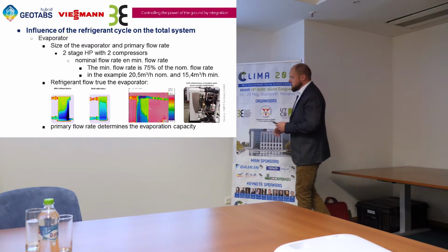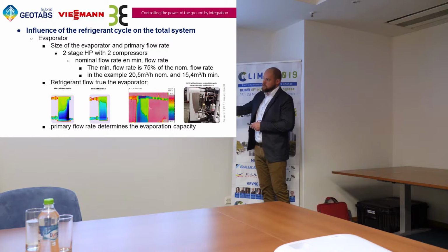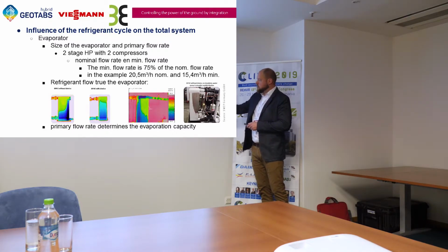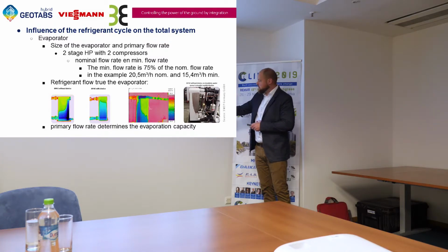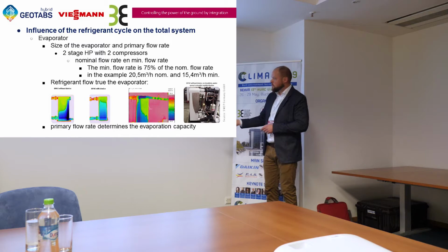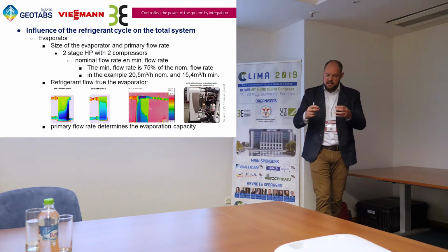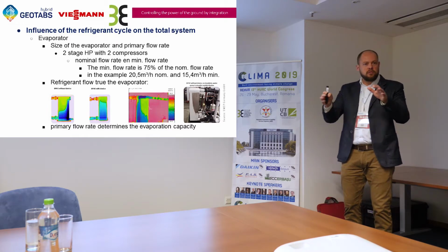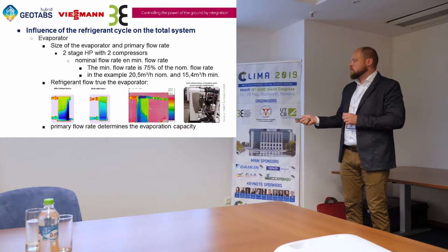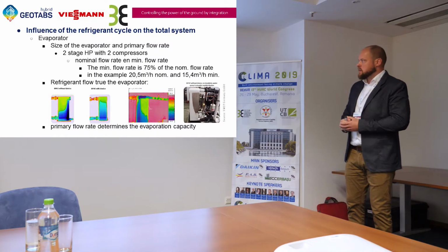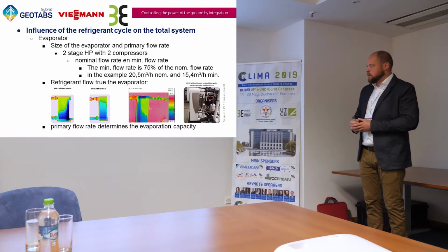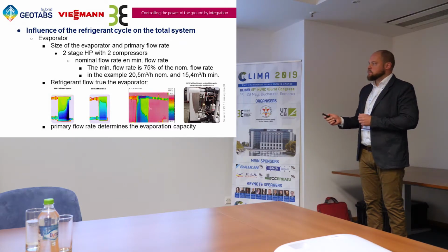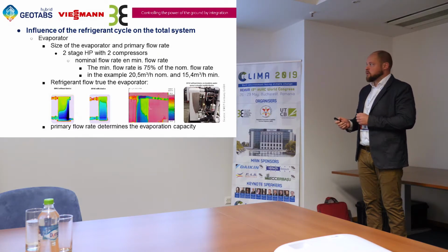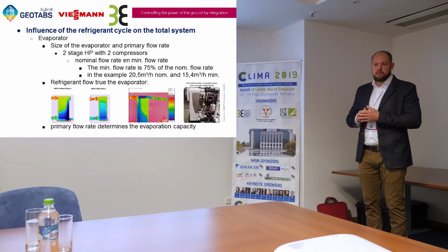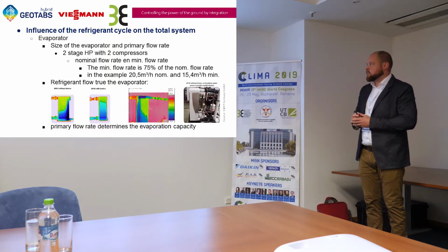We also have a test here. You can see it's about SWEP, the constructor of our heat exchangers. They did a test with water, sprinkled water onto the system, and you can see the freezing pattern according to this picture here. They also added a special device inside the heat exchanger to equalize the flow of refrigerant throughout this evaporator, so you have a much more stable flow, and that means that we have a better working of the heat pump. So it's very important that when you select a heat pump and you calculate the evaporator flow rate, that you keep in mind that when the heat pump is a two-stage heat pump, you keep in mind the minimum flow rate of about 75% of the normal.